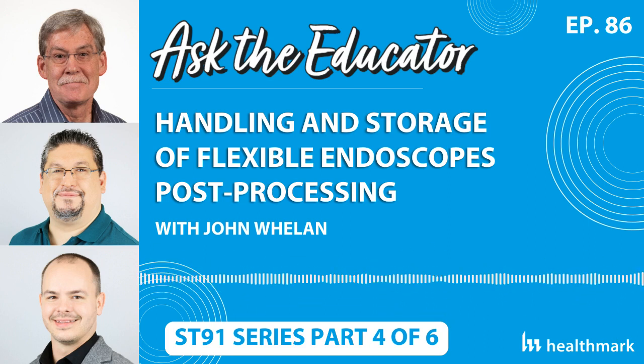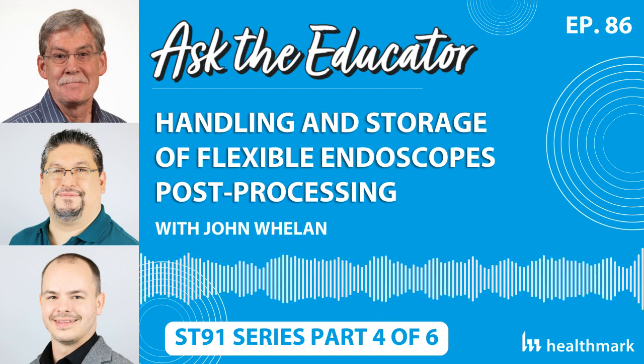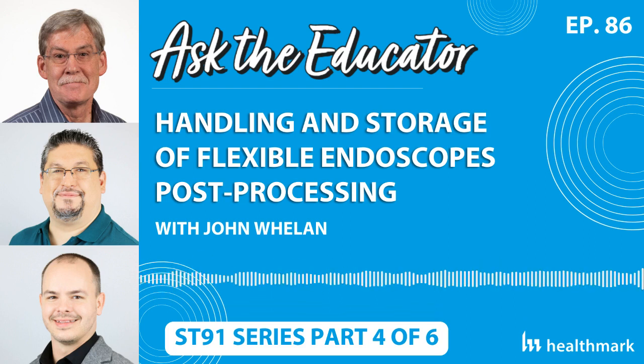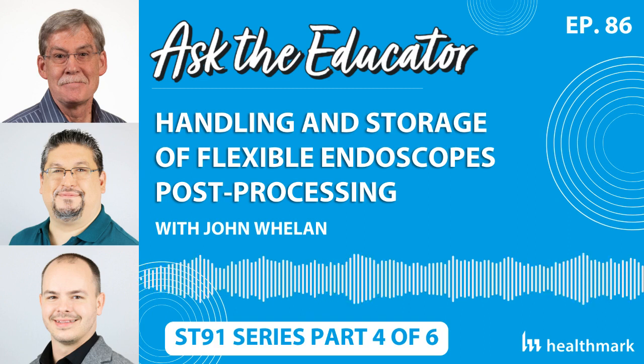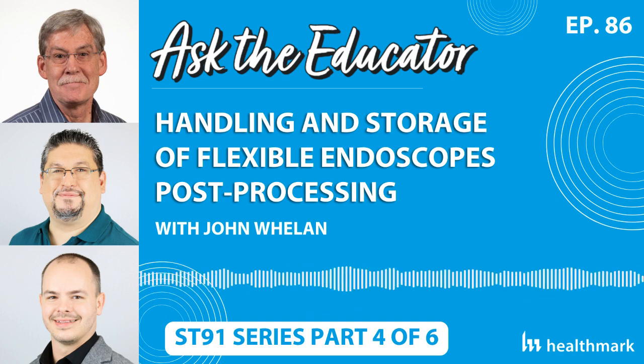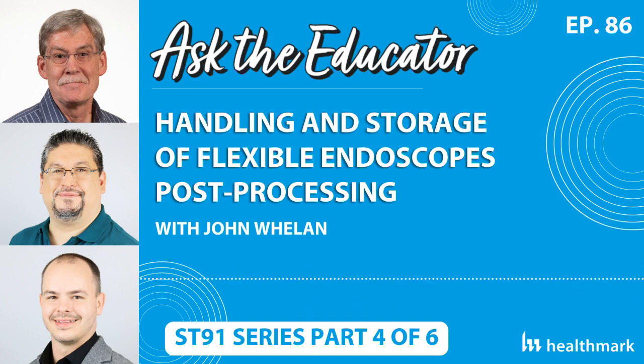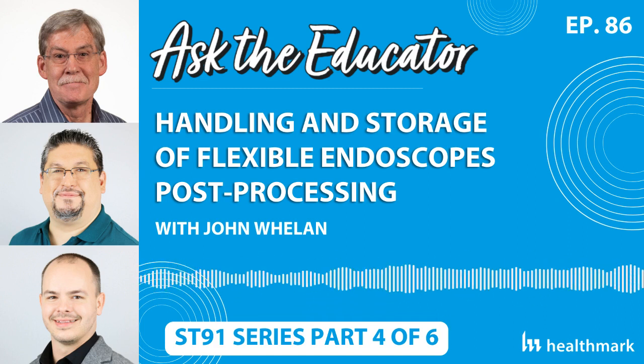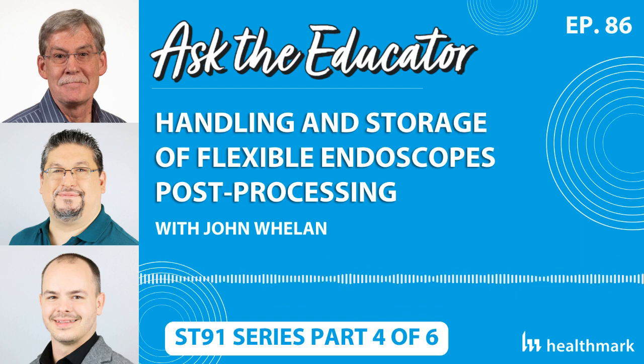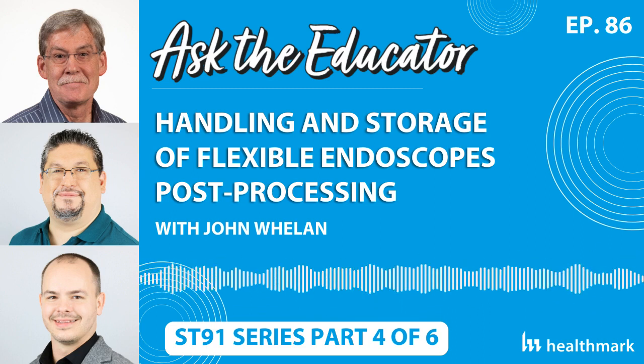When it comes to drying cabinets, yes, they're preferred. That doesn't mean they're obligatory. And so what should be gone, though, is the days of having famously built-in laminate cabinets that have no ventilation other than a little circular passive air vent in them. That was a standard for years that you saw. You need to have air blowing into the cabinet to dry the outside of the scope and create a drying environment, if you will, for a scope that's hanging there.